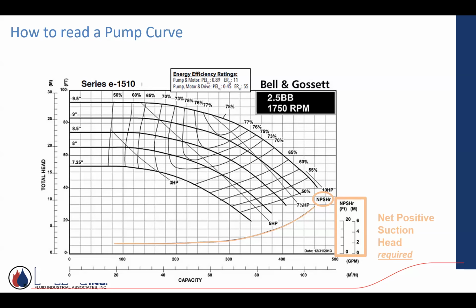One's called R, it's established by the pump manufacturer. He knows his design. And then the next one is A, what's available? What does the system provide me? We'll get into this a little deeper later on. But just from an information standpoint, when you look at this pump curve, you've got diameters, horsepower, efficiencies. Off to the right, you have this NPSH required. This is the manufacturer saying, make sure you give me this much net positive suction so that I don't cavitate, I don't damage the pump.